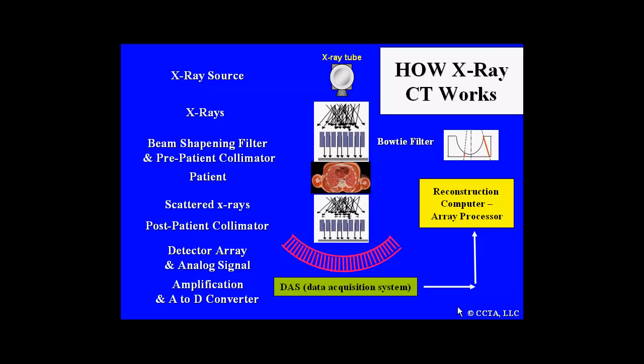This is an overview of the CT scanner. An x-ray source sends out a series of x-rays, which are somewhat scattered and are then collimated and shaped by a pre-patient collimator, usually called a bowtie filter. This reduces overall radiation dose and makes it much more uniform when the x-rays are incident upon the patient.